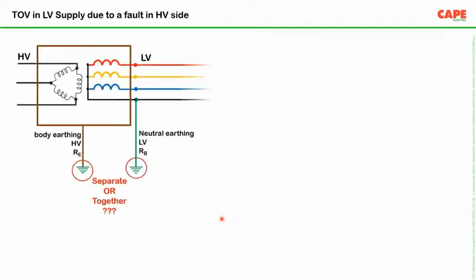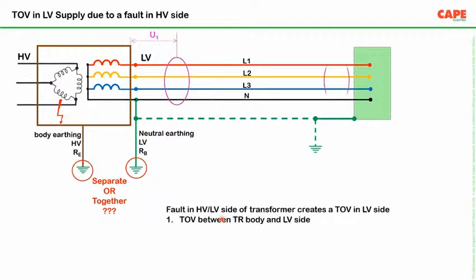Say for example, the picture I am showing has a transformer. You have the high voltage side and the low voltage side. RE stands for the earthing of the high voltage side, RB stands for the low voltage side. Now these two earthings are separate or together. This is actually a technical question where the designer of the installation has to think, has to calculate, and has to apply his mind and do a proper job.